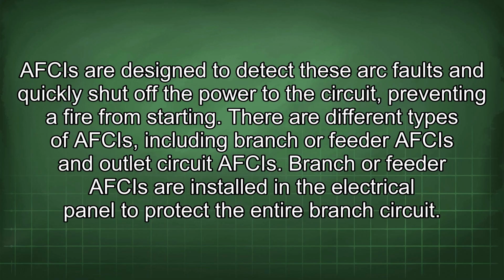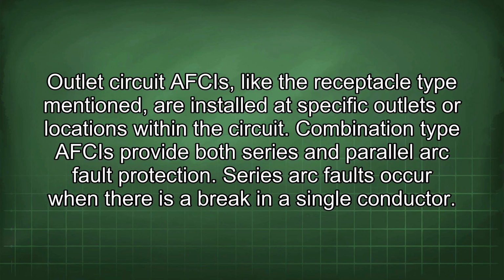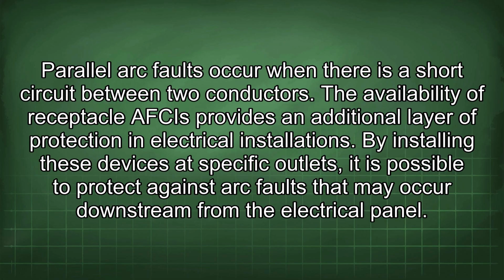There are different types of AFCIs, including branch or feeder AFCIs and outlet circuit AFCIs. Branch or feeder AFCIs are installed in the electrical panel to protect the entire branch circuit. Outlet circuit AFCIs, like the receptacle type mentioned, are installed at specific outlets or locations within the circuit. Combination type AFCIs provide both series and parallel arc fault protection. Series arc faults occur when there is a break in a single conductor. Parallel arc faults occur when there is a short circuit between two conductors.